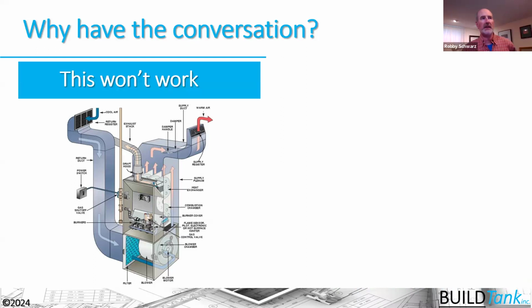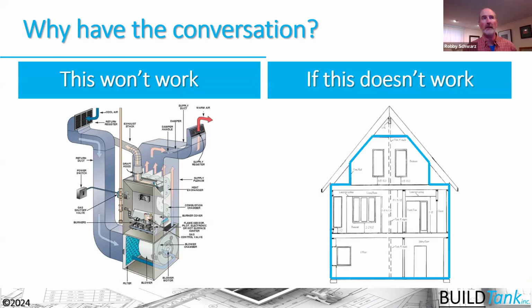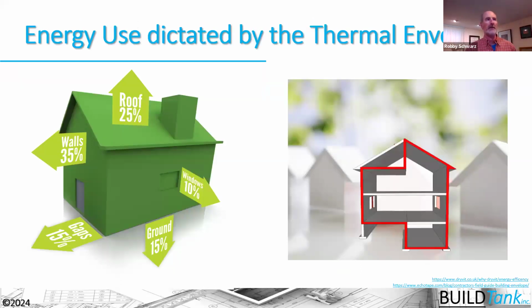So when we begin this conversation, we have to have a clear understanding that our HVAC system simply will not work unless we have a sound building thermal envelope. And that's why the code really focuses on the building thermal envelope, having that continuous boundary condition between conditioned space and unconditioned space, mainly built from the alignment of our air control layer and our thermal control layer. But we also need to remember that we're talking about assemblies of things and kind of a belts and suspenders approach. And we went over that in our last trainings, how the code is really looking at the building thermal envelope there.